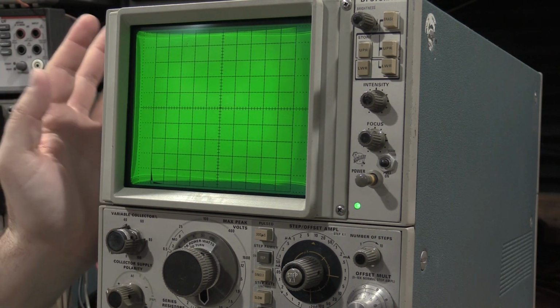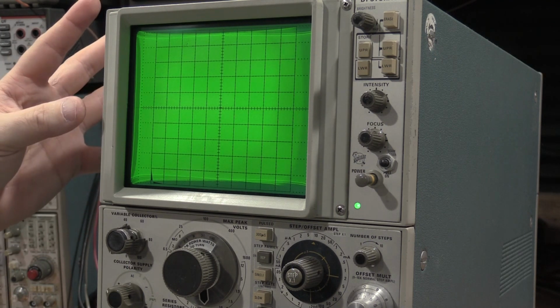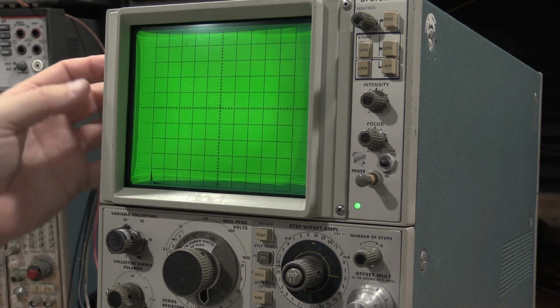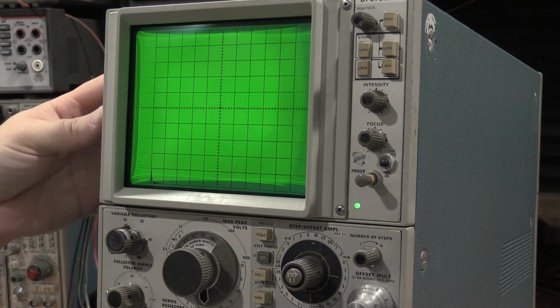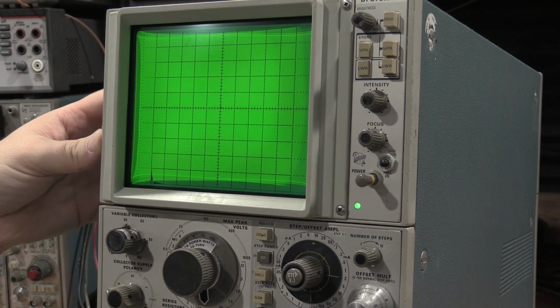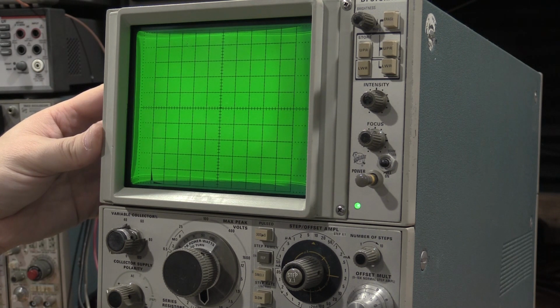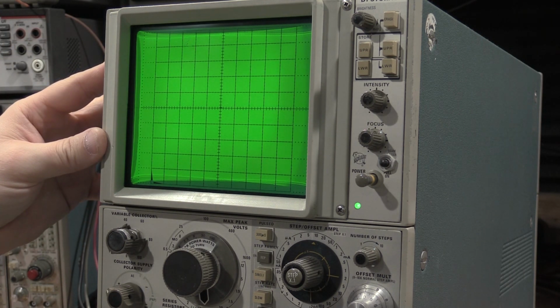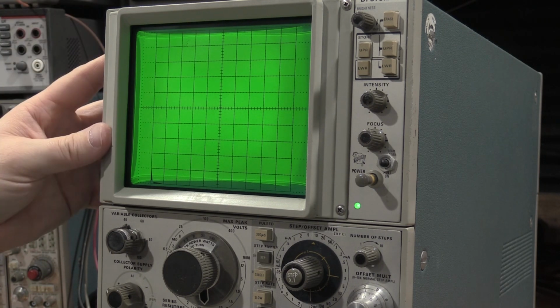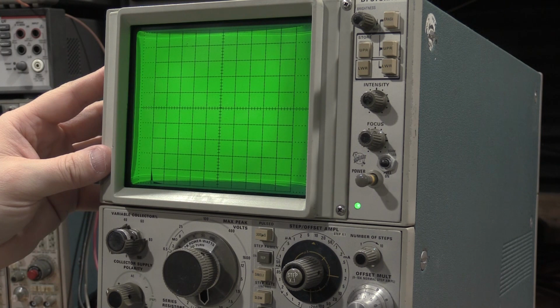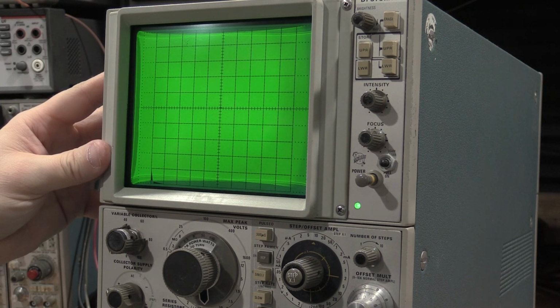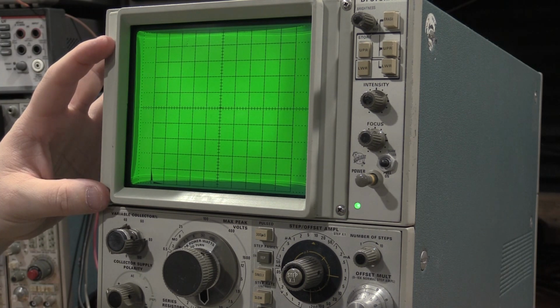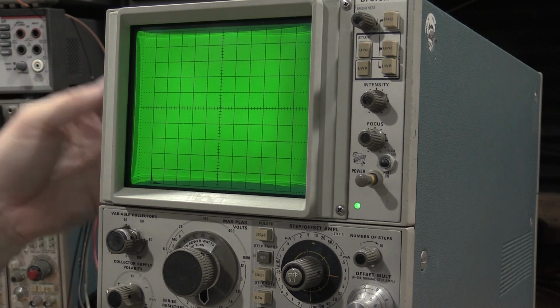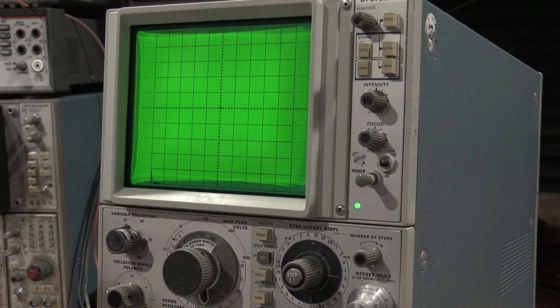One thing to note is, from what I've been told, and correct me in the comments if I have been told incorrectly, when you ordered a storage tube from Tek, it came with a card that said what you should set the storage voltages for. Obviously, we can't order new storage CRTs from Tek. They don't make them anymore. Unless you find one brand new old stock, which is very unlikely, the best thing to do is, in the calibration manual, the storage voltages that are listed should not be taken as absolutes. They should be taken as a guide. If it looks like the tube's being stressed because it's really bright and the storage is really bright, back it off a little bit. Dimmer is better for CRTs. Hammering them just burns in the phosphor a little bit.